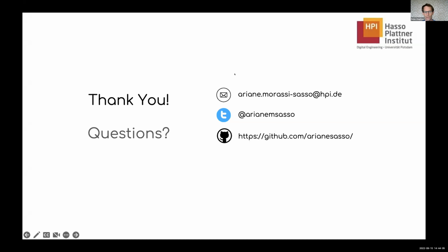Thank you. And Alex just adds a small comment saying it's the mean error rather than the mean absolute error that's used in the AAMI standard. Yes, that's true. And that's something we also noticed, but also the problem with the standard is there's still a discussion, I think, on how to actually evaluate machine learning models for blood pressure estimation. We decided to use the MAE just because of the nature of the measurement and to compare to other scientific work. Maybe I should not have used the AAMI since they actually use mean error.